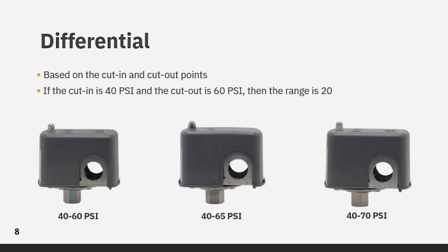Differential, also known as the dead band, is the difference or spread between the cut-in and cut-out points. On most switches, the differential between the cut-in and cut-out can be adjusted. However, some switches have fixed, non-adjustable differentials. Some applications require a wider or narrower spread between the pump-on and pump-off set points. To adjust, turn the nut on the small spring clockwise to raise only the cut-out pressure. Turning it counterclockwise will lower the cut-out pressure only.